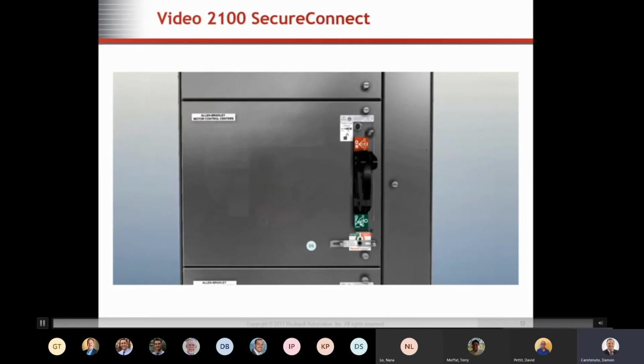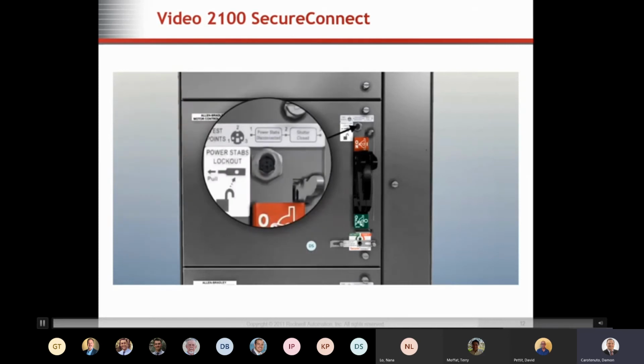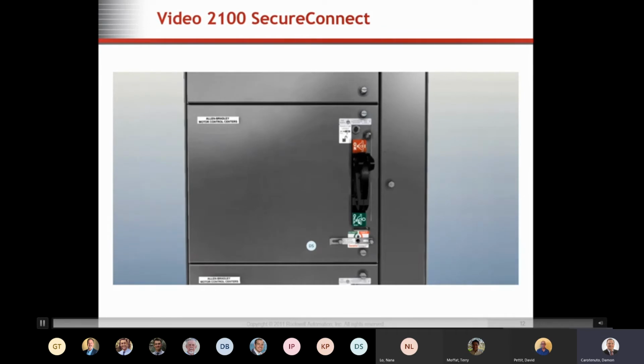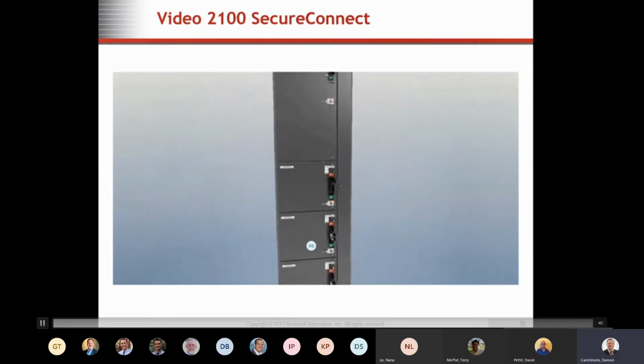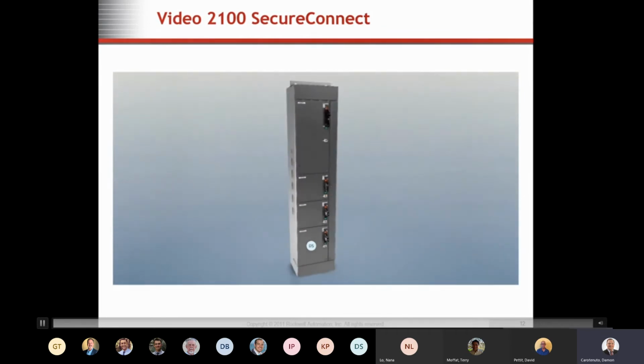You can also verify the electrical power is disconnected using the test ports in the front of the unit. The limit switch verifies that the shutters are closed properly, while the continuity check verifies that the stabs are fully withdrawn into the stab housing and in a safe position. At this point, you can continue to follow your safety procedures to work on the unit without having power inside the unit. With SecureConnect in your CENTERLINE Motor Control Center, you can help enhance your overall electrical safety program.